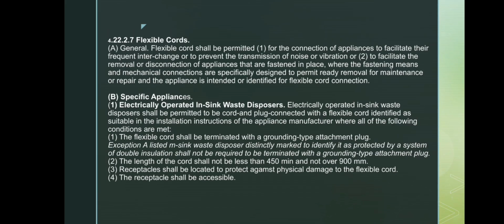Next, we move to flexible cords under section 4.22.2.7. First, flexible cords are allowed in two situations: when an appliance needs frequent movement or when the cord helps reduce noise or vibration, and when the appliance is fastened in place but designed to be easily removed for maintenance and the manufacturer identifies it for flexible cord connection.